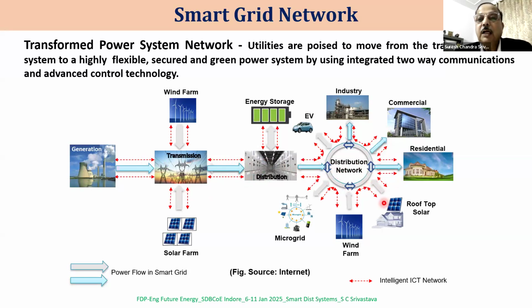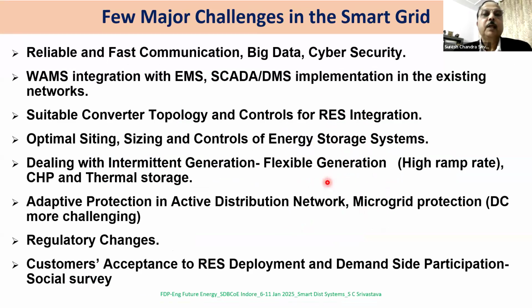The second reason is the converter interface: renewable sources reduce the fault level. The initial fault level is very high for a few microseconds or milliseconds, but the final fault level is quite low; they limit the fault level. So it becomes very difficult to distinguish between a fault and normal operation. These are the two challenges the protection system is going to face: reduced fault level and bidirectional power flow, which make it difficult.